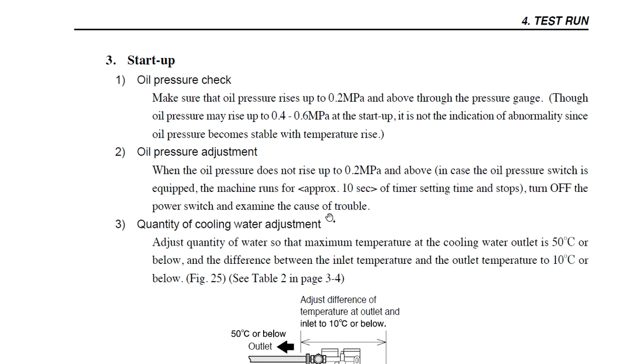In the first startup, what to check after overhauling or maintenance: we check our oil pressure must rise to 0.2 megapascals, which converted to bars is 2 bars. That is the reading we must see.